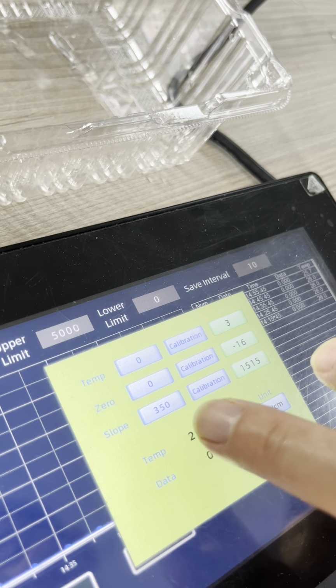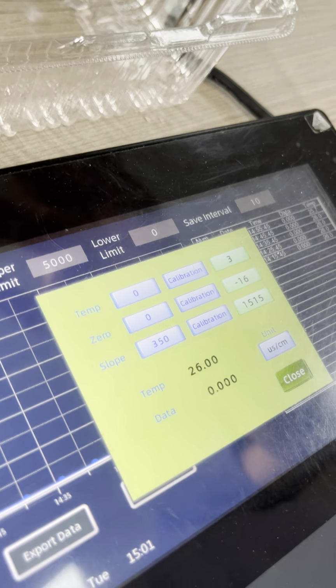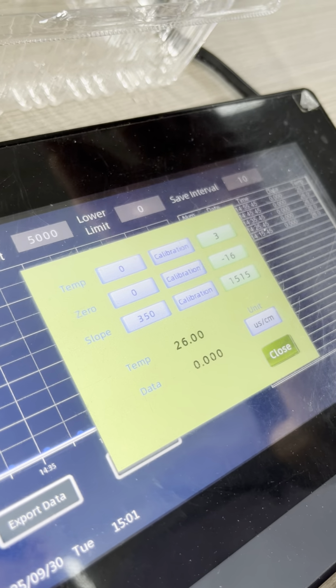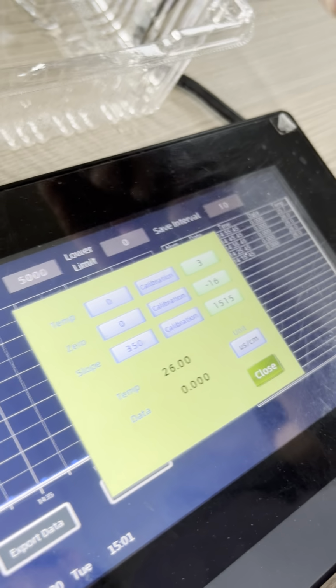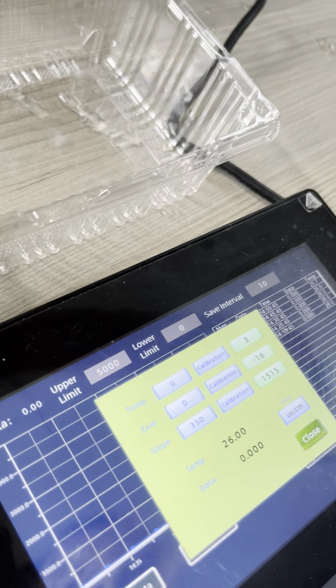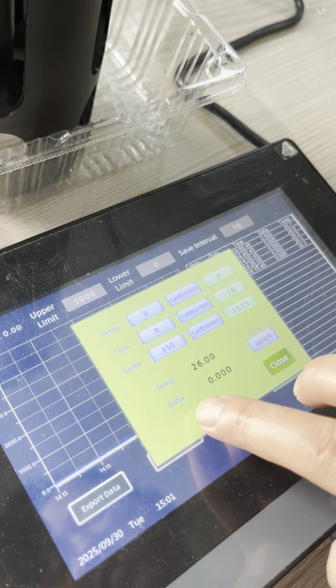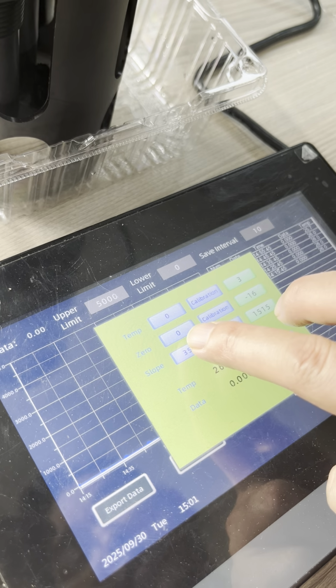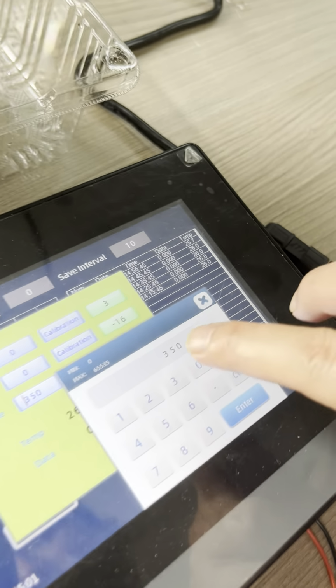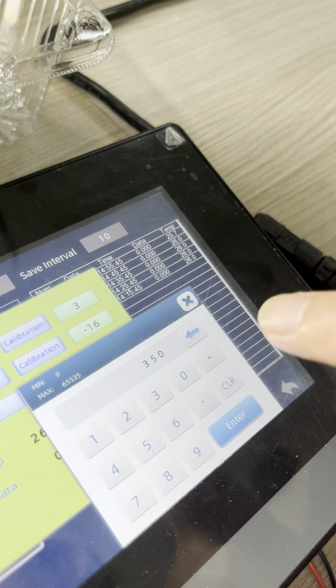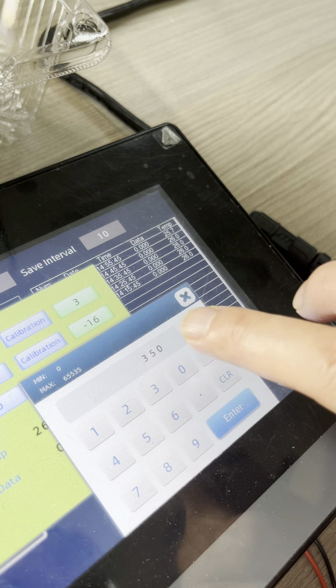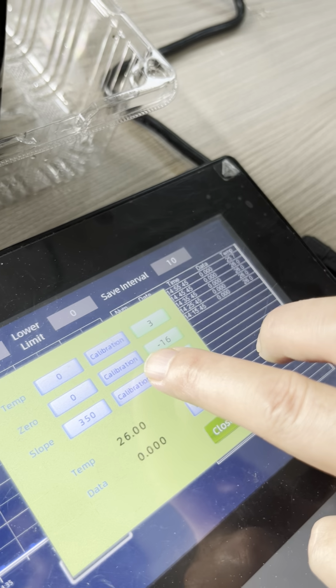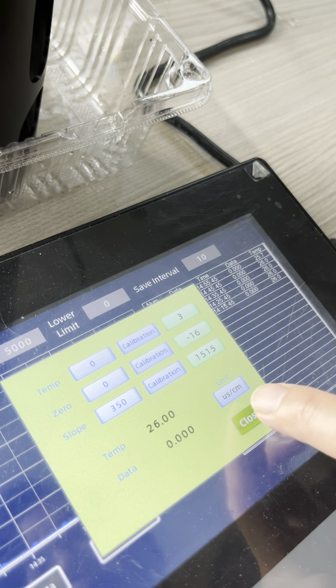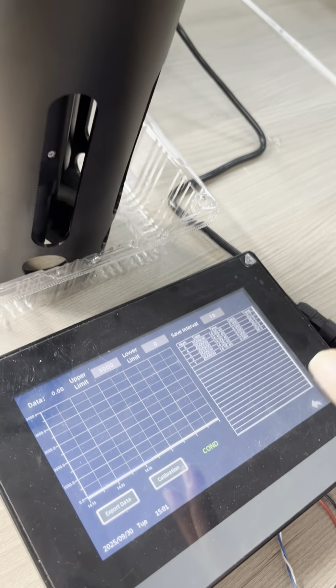For the slope calibration, we need to put the sensor into standard solution of 35 PSU. You need to put the sensor into the standard solution. After 3 minutes, the data will be stable. Then here, you click here, you input 35 times 10, that is 350, and click enter, and click calibration. Now the calibration for the salinity is done.